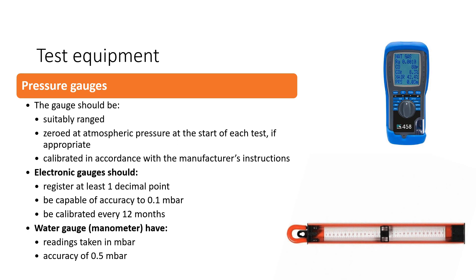Electronic gauges must be more accurate than U-gauges. They should register at least one decimal point — for example, a reading of 8.3 millibar shows it's capable of registering a decimal point. Electronic gauges should be capable of an accuracy to a tenth of a millibar (0.1 mbar), and they should be calibrated every 12 months. U-gauges must have readings in millibar and must have an accuracy of half a millibar.